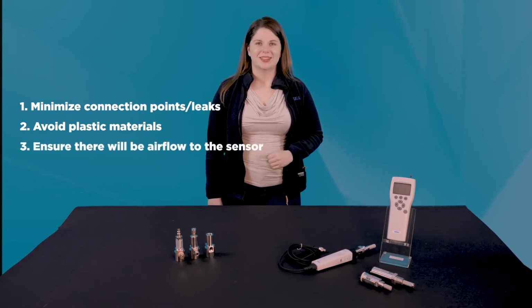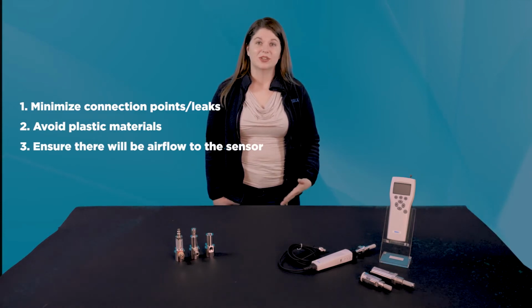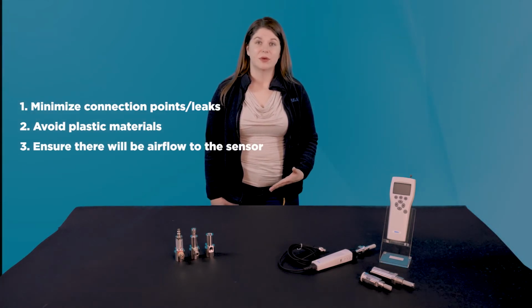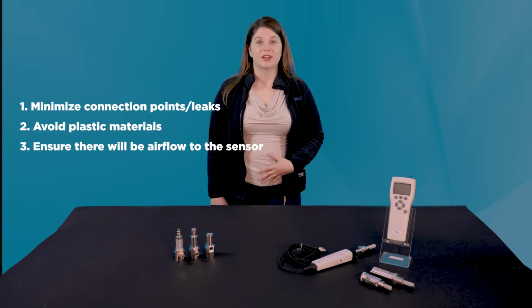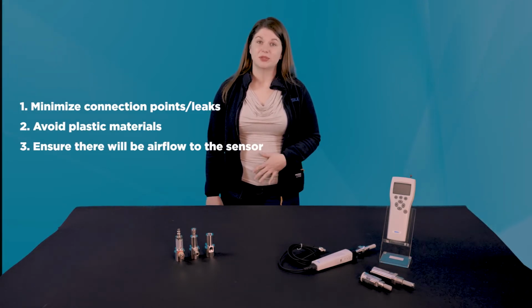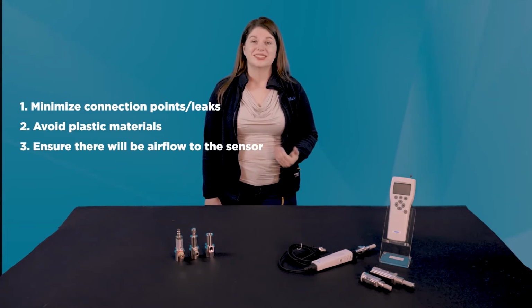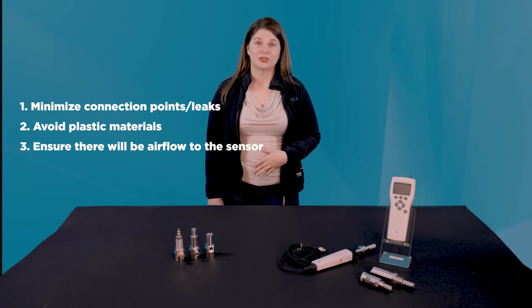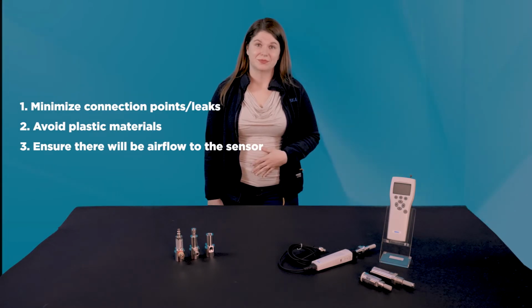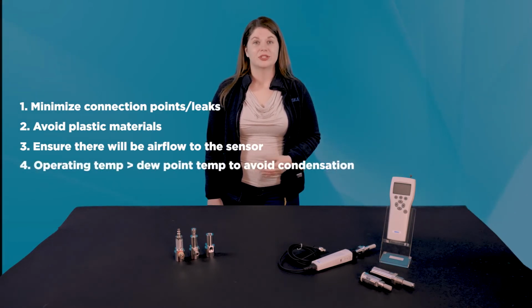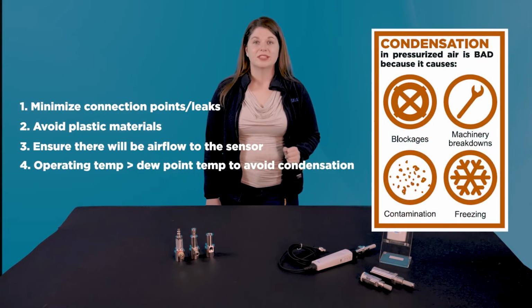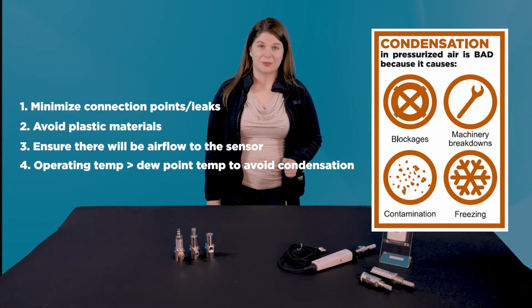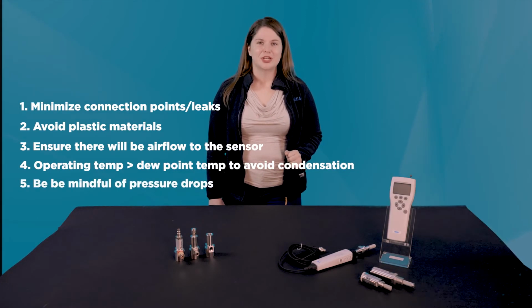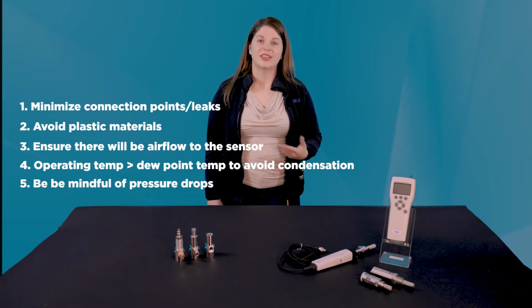Third, avoid dead ends with no airflow. At best, installing into a dead end will mean a very slow response time for your measurements, but depending on the system, construction materials, and temperature variances across the system, the dead end air may simply never reflect the moisture content of the air in the rest of the system. Fourth, ensure that the gas temperature stays higher than the dew point at all times in order to avoid condensation. This sometimes means heated or insulated tubing. Fifth, be mindful of pressure changes and pressure drops between the sensor and the air you care about measuring, since dew point is pressure dependent.